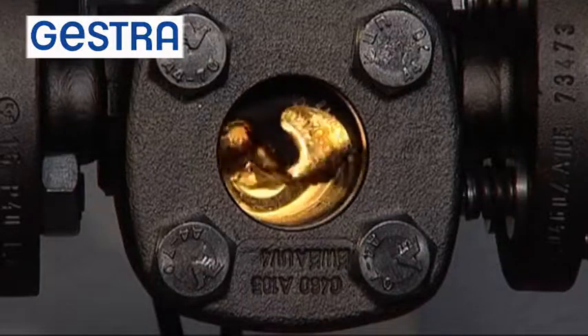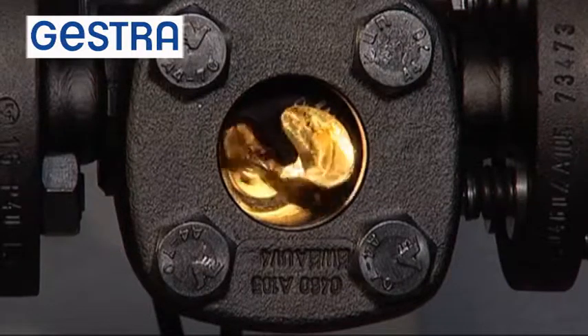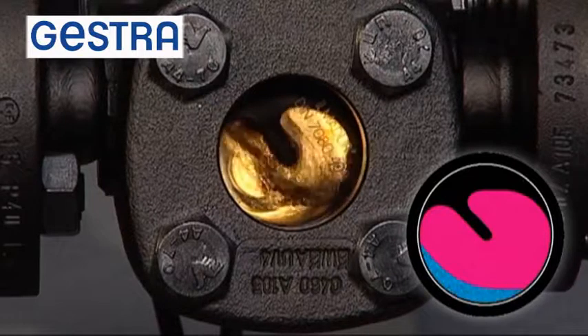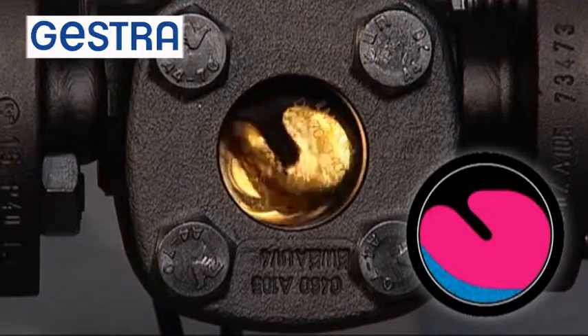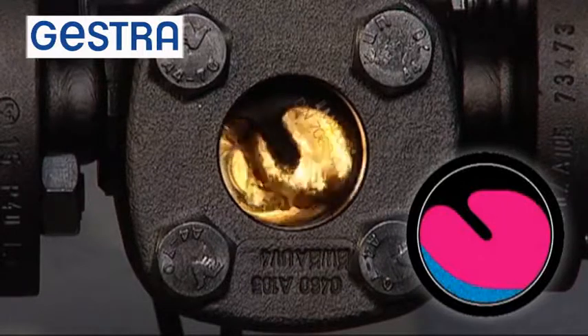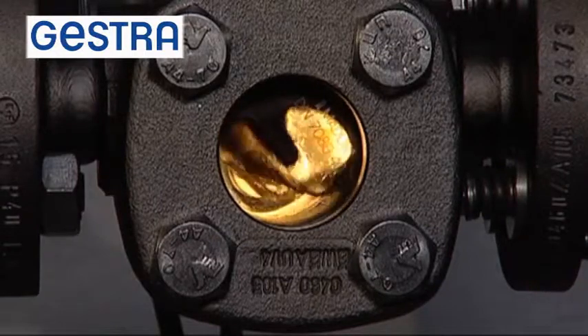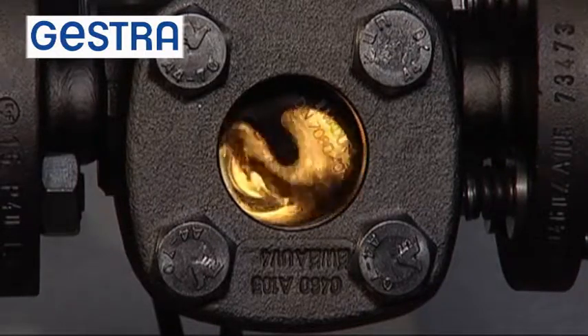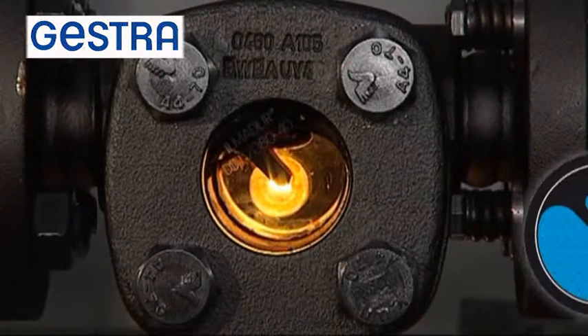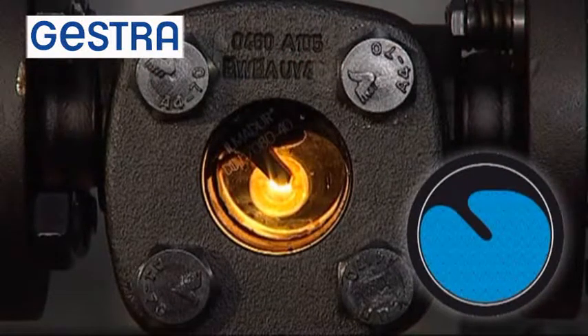Now the float trap is opened with the aid of its float lifting lever, so that steam is forced to flow through the steam trap. The deflector immediately emerges from the water, since the steam passing through now presses the condensate downwards into the siphon. This is a clear indication that the steam trap is causing loss of steam. Here, the Vaporscope is completely filled with condensate, which points to a banking up of condensate in the trap.